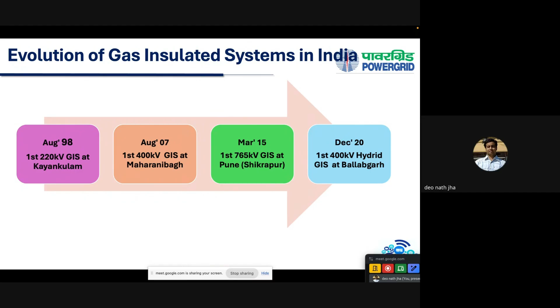These gas insulated systems have come into vogue now in India because more and more power centers or substations are coming up in urban areas where land acquisition is a big issue, and we have to create substations in congested spaces. So the country has gone ahead with planning gas insulated switchgear, which requires about one third the space of an air insulated system.